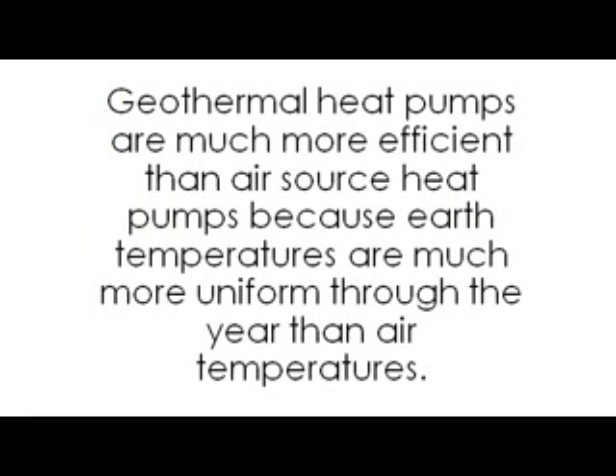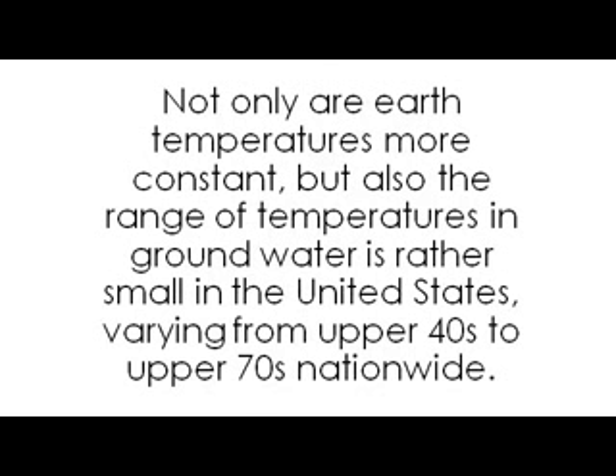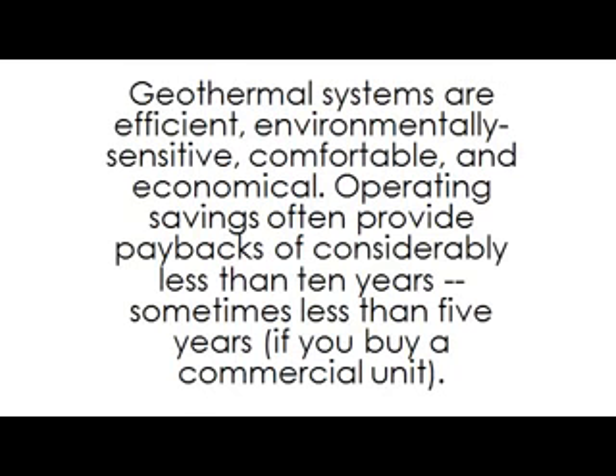Geothermal advantages. Efficiency. Geothermal heat pumps are much more efficient than air source heat pumps because earth temperatures are much more uniform through the year than air temperatures. Not only are earth temperatures more constant, but also the range of temperatures in groundwater is rather small in the United States, varying from upper 40s to upper 70s nationwide. Geothermal heating and cooling makes sense.